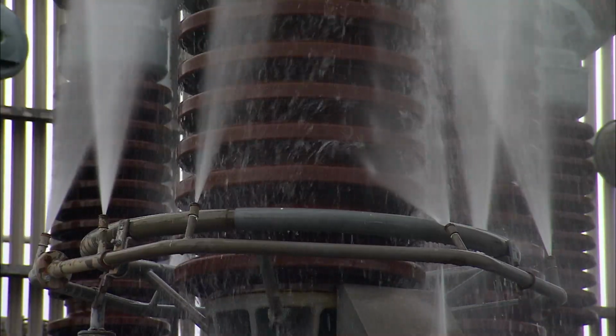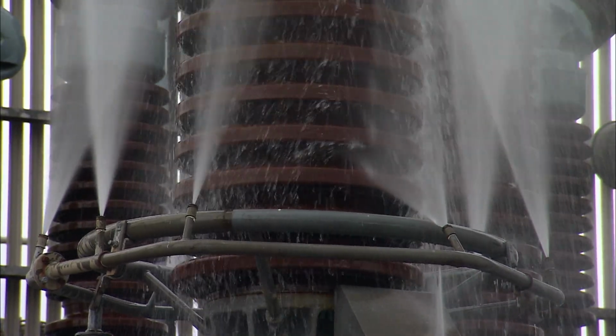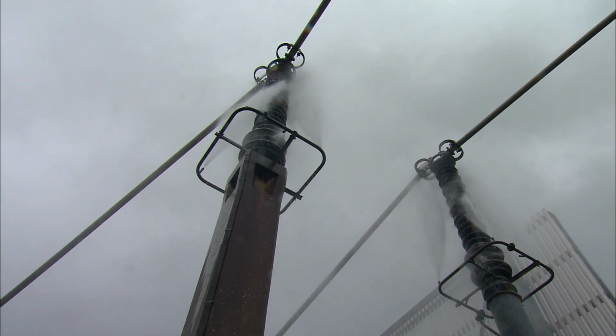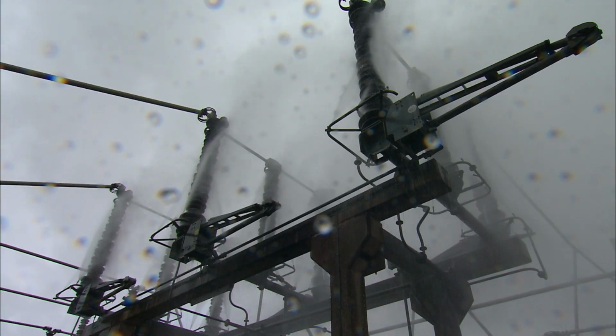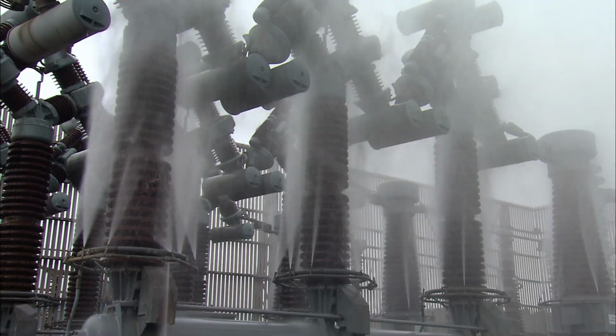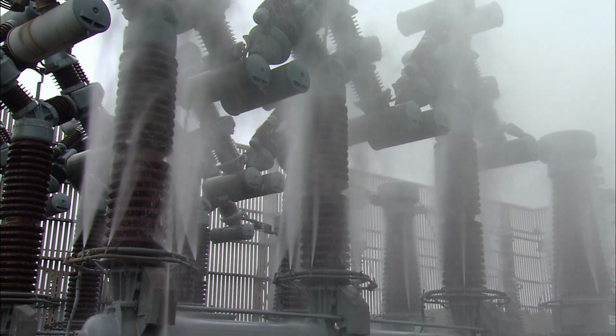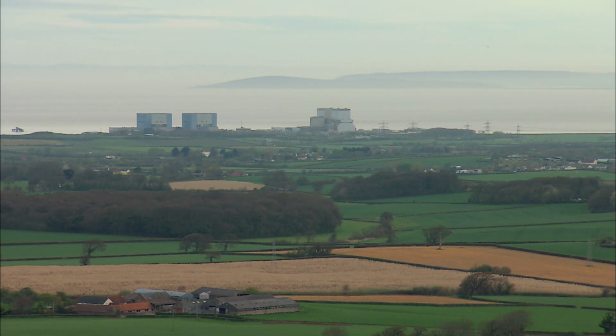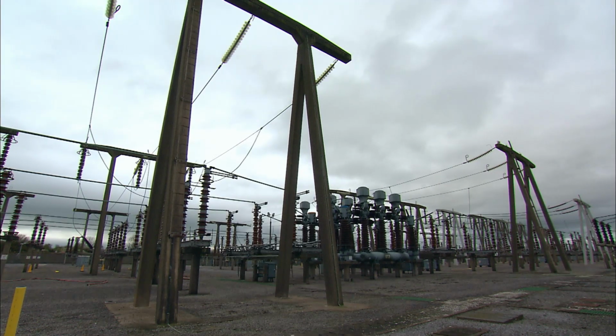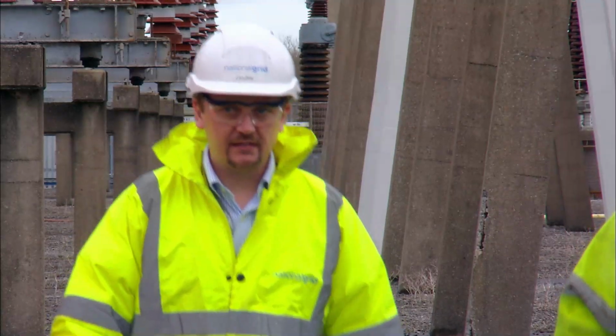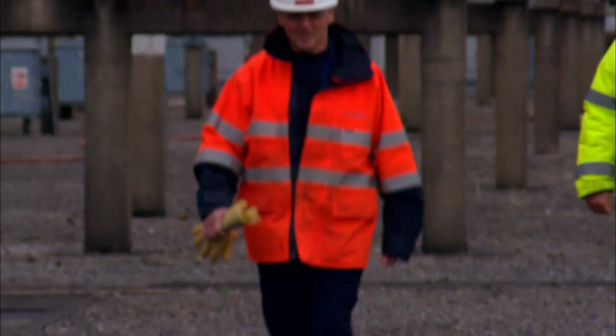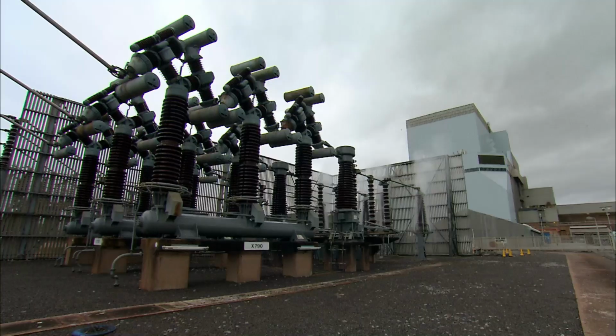Unlike a manual wash, this system can run every 2 hours, day and night. And if a 400,000 volt flashover does happen, there won't be a man on the receiving end. Hinkley Point Power Station uses the sea for cooling water, but that puts its substations in the way of the salty air from the Bristol Channel. So, for over 25 years, Frank and the team have been doing something you should never do at home: mixing electricity and water to keep the power flowing smoothly.